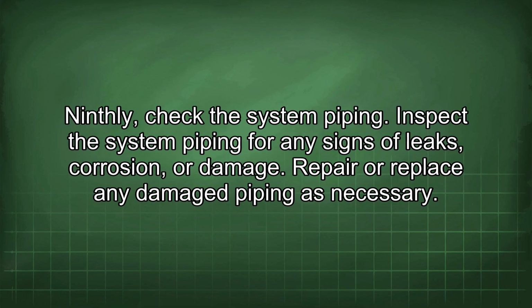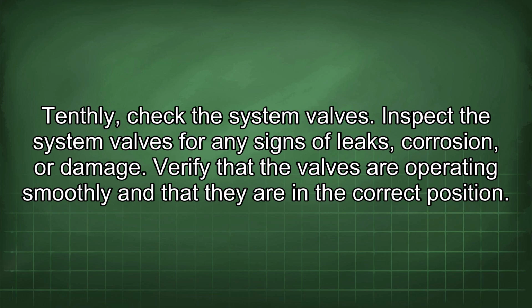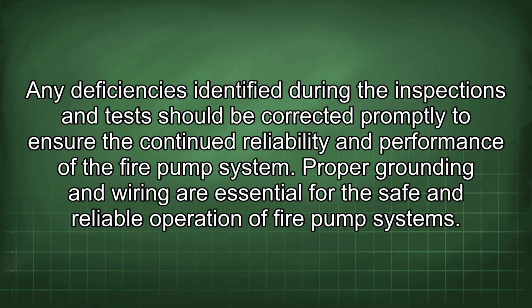Ninthly, check the system piping. Inspect the system piping for any signs of leaks, corrosion, or damage. Repair or replace any damaged piping as necessary. Tenthly, check the system valves. Inspect the system valves for any signs of leaks, corrosion, or damage. Verify that the valves are operating smoothly and that they are in the correct position. Any deficiencies identified during the inspections and tests should be corrected promptly to ensure the continued reliability and performance of the fire pump system. Proper grounding and wiring are essential for the safe and reliable operation of fire pump systems.